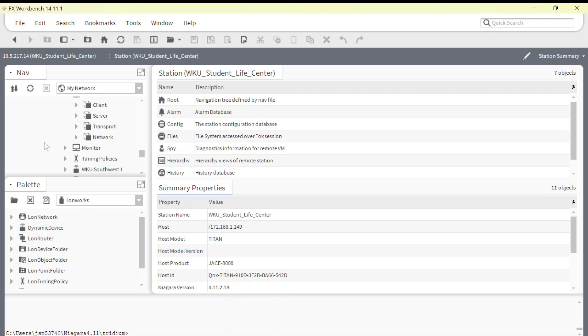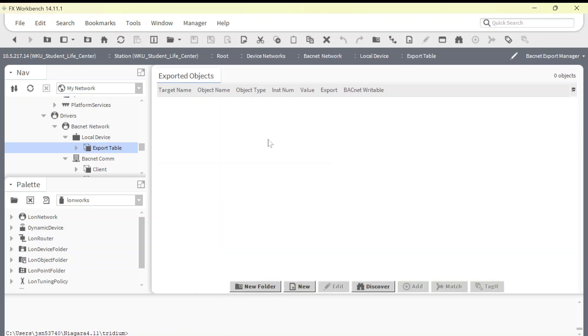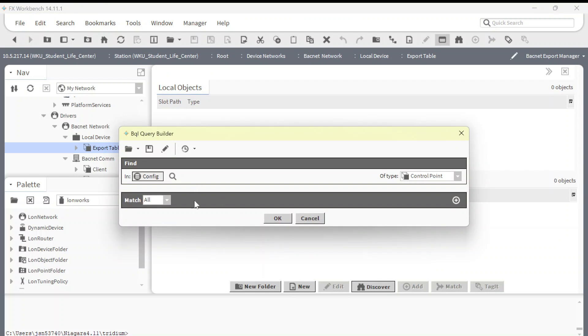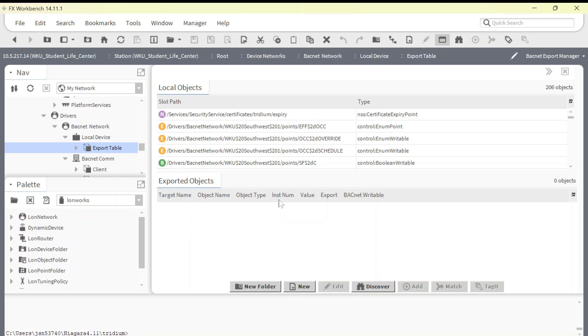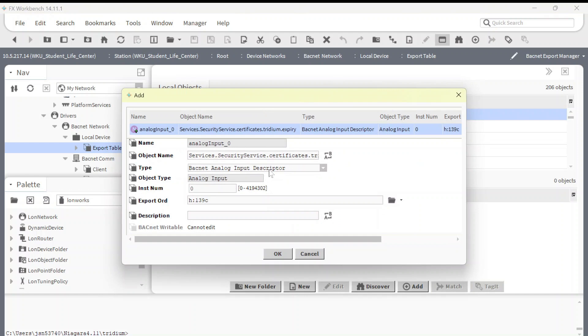After we did the discovery on the device and saw some issues, we had to go back in to do the work to actually get the points available for discovery. What you're going to want to look for is underneath your BACnet network — go to the local device, then select the export tables. This is where you're going to pull those points in. You can simply hit the discovery button and it's going to discover everything on that Jace.